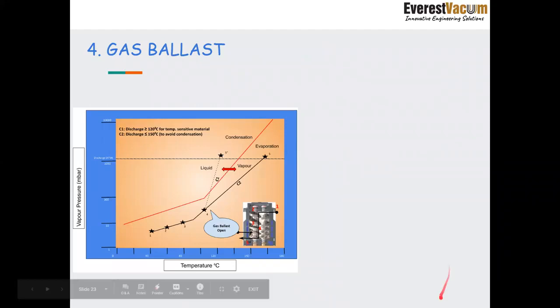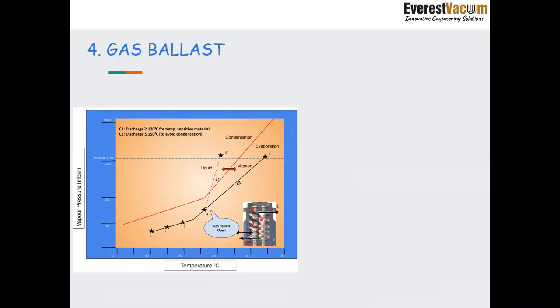As you can see in the photograph, in this diagram, there are stages 1, 2, 3, 4, and 5. From stage 1, the vapors come into the pump, then pass through certain stages and finally get vented out from point number 5. So during the stage from 1 to 5, there is continuous compression happening inside the pump. So at point 4, what Everest does is we purge a certain amount of gas into the pump so that the vapors which have entered into the pump don't convert into the liquid.